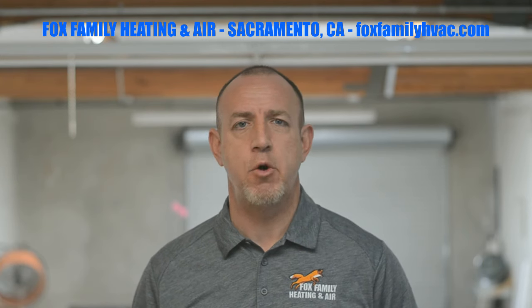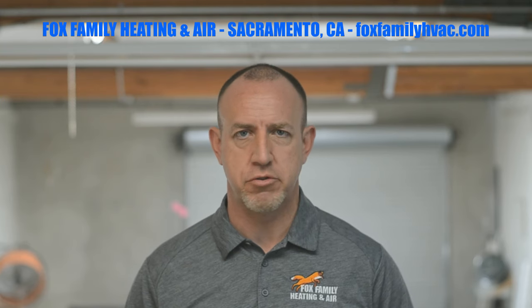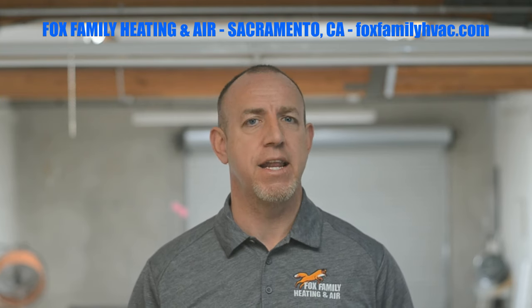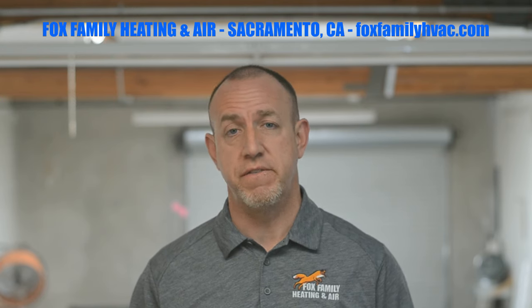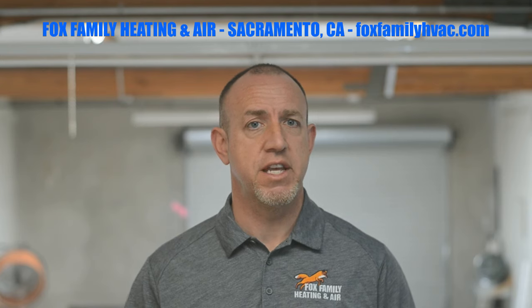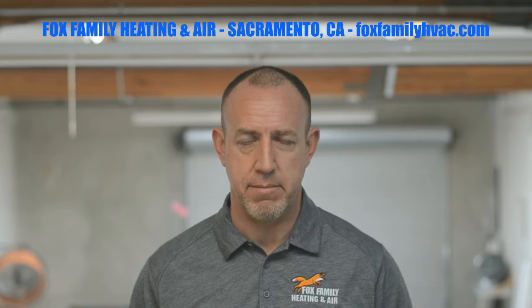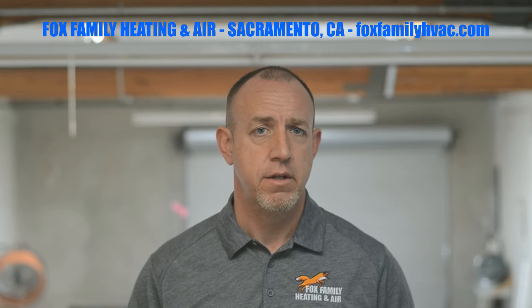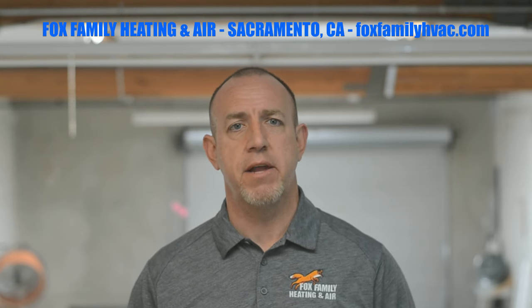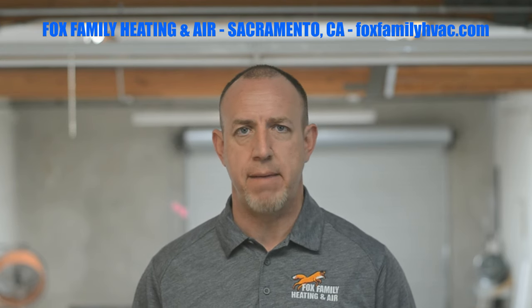Danger. I want to reiterate that I'm only giving homeowners and technicians some ideas here as to why the breaker is tripping. I'm not advising anyone to go out and try to fix their system on their own. Working with high voltage can cause severe injury and even death to even the most experienced technicians. A breaker trips when there is too much power consumption or current at any given time. The wire from the AC to the panel heats up enough that it trips to stop a potentially hazardous situation from happening.